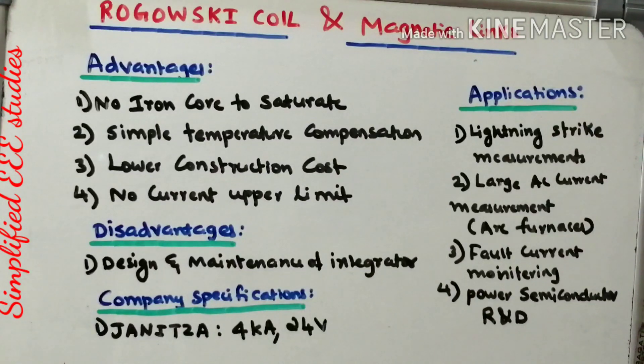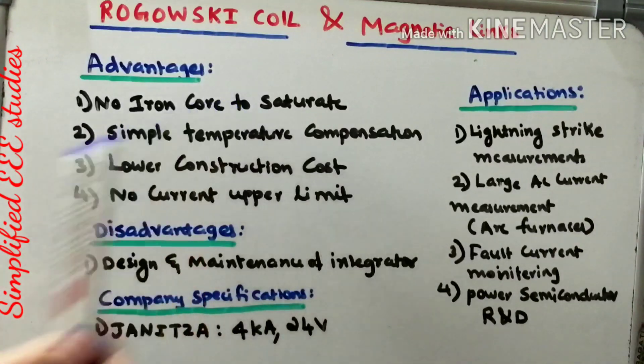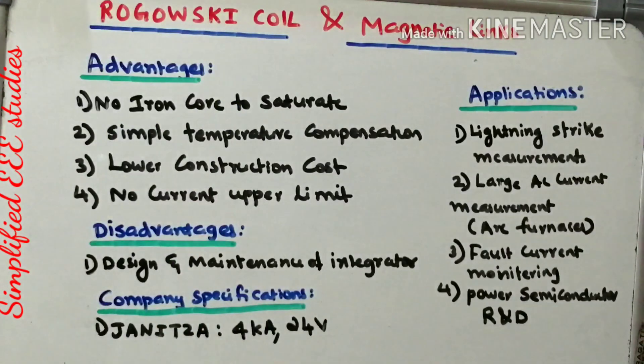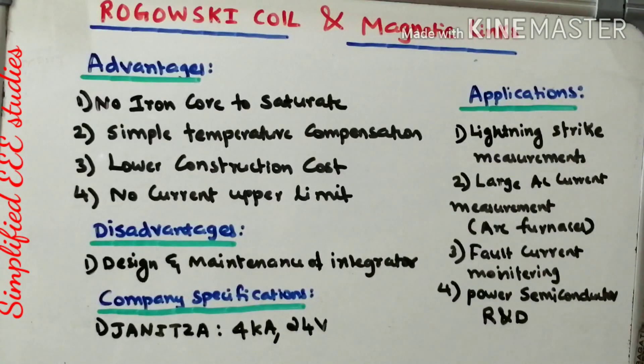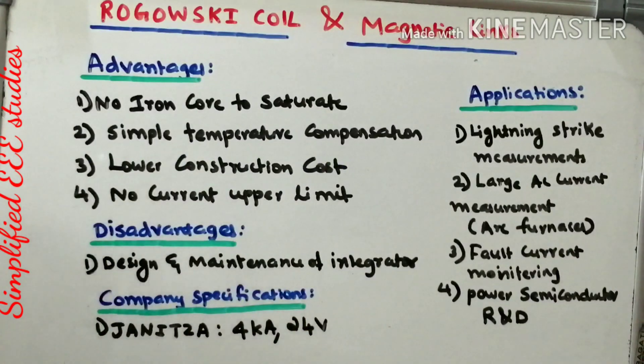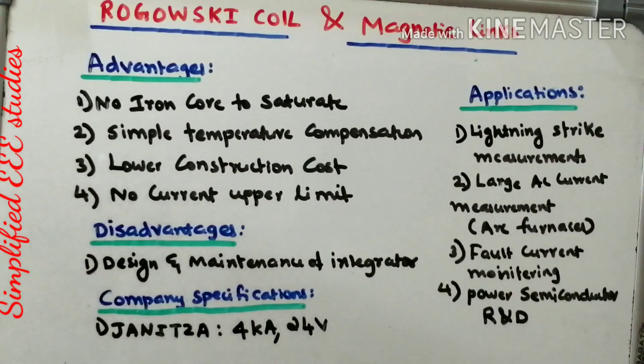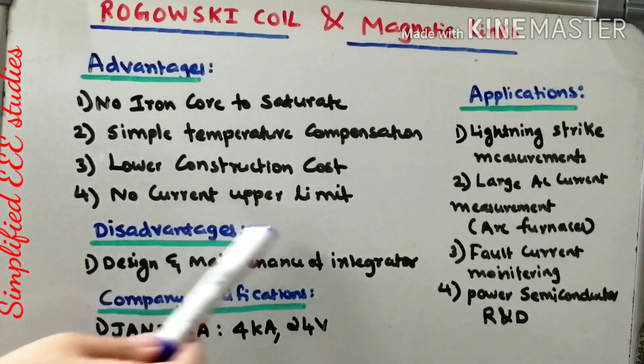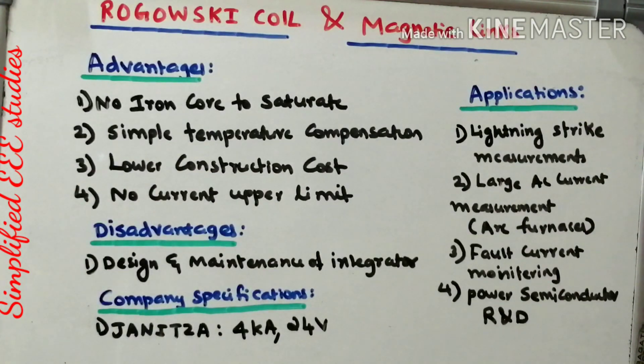Now let us discuss the advantages of the Rogowski coil. First, there is no iron core to saturate, so iron core loss is negligible. Second, temperature compensation is simple. Third, construction cost is low since it is essentially a toroid. Fourth, there is no upper current limit. These are the key advantages of the Rogowski coil.